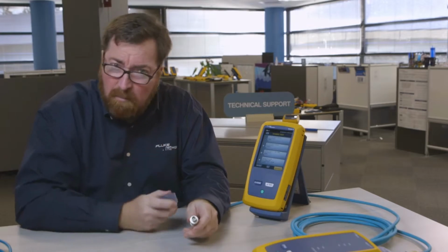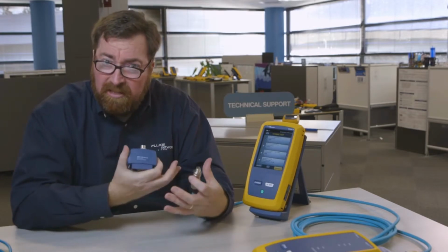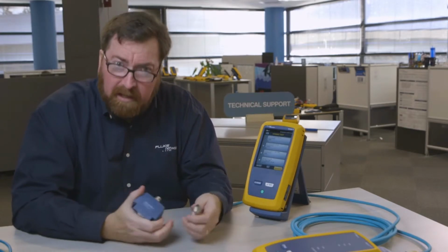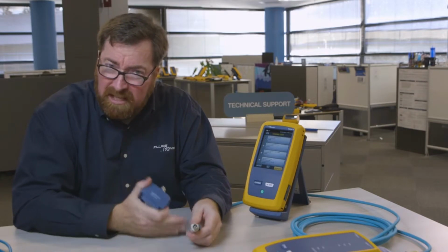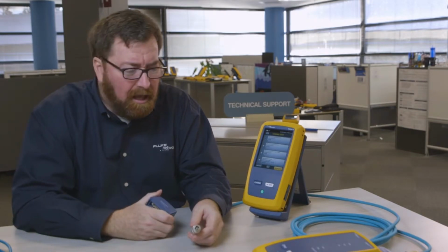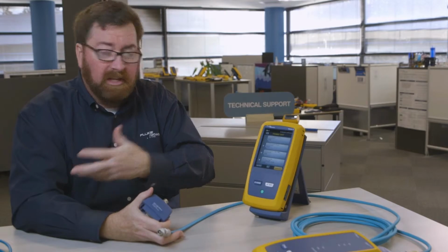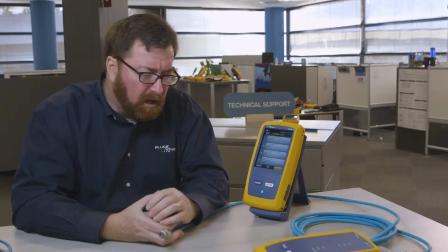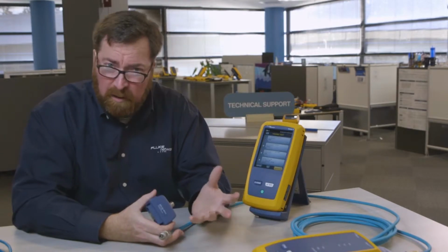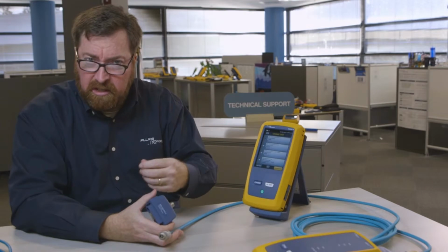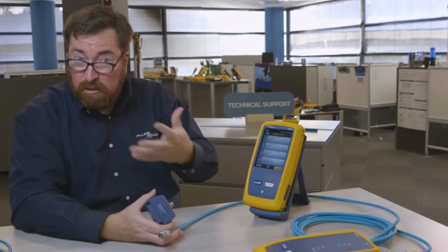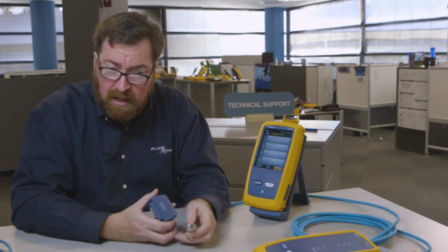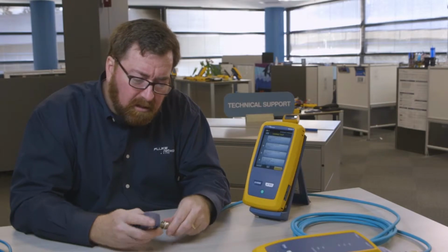And the E in MICE has to do with the electronic environment. There are 3 levels, E1, E2, E3. Representing a standard office would be an E1 environment. E2 would have more interference. In an E3 environment, perhaps in an industrial environment where you may have arc welding machines or large motors, sources of electromagnetic interference. So I want to test this connector.